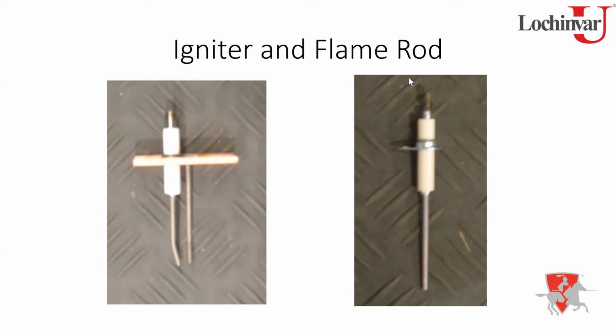So, like we were talking about, we typically like to use some type of Scotch-Brite. Not a big fan of metal wire brushes because, again, I'm not trying to reshape this igniter or flame sensor. I'm just trying to knock the dust off it a little bit, just knock the surface off. So a lot of people, I'll tell you, Scotch-Brite I'm good with.